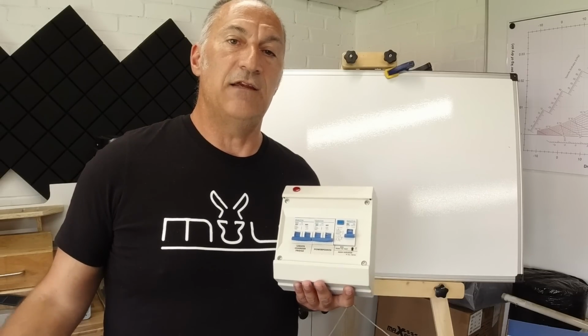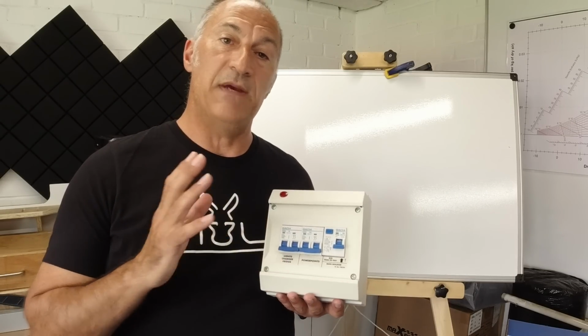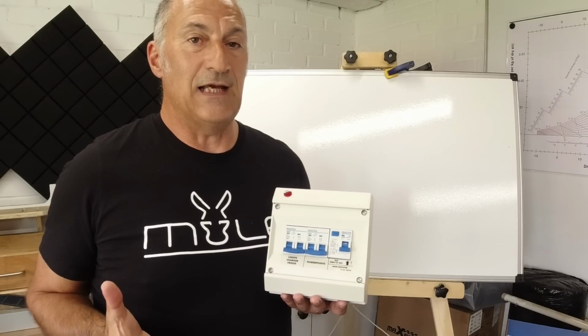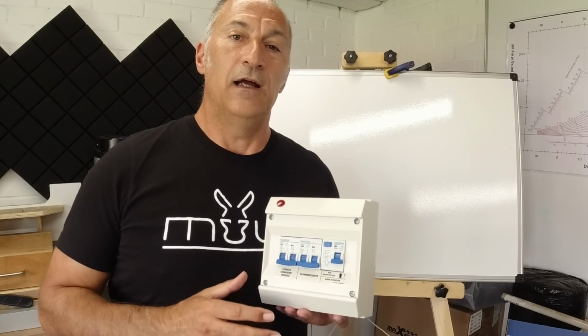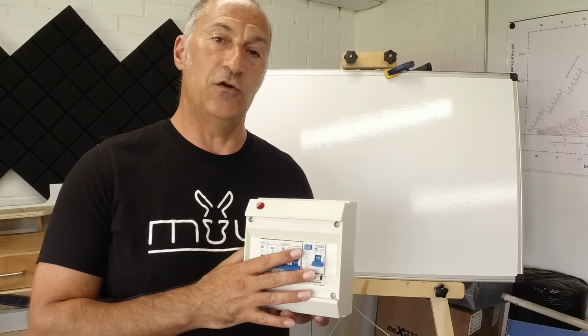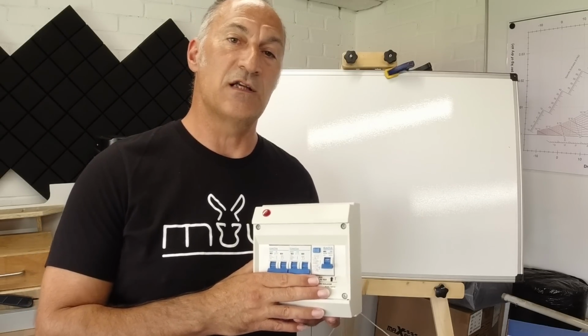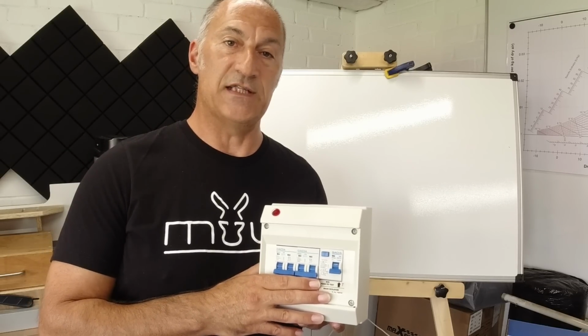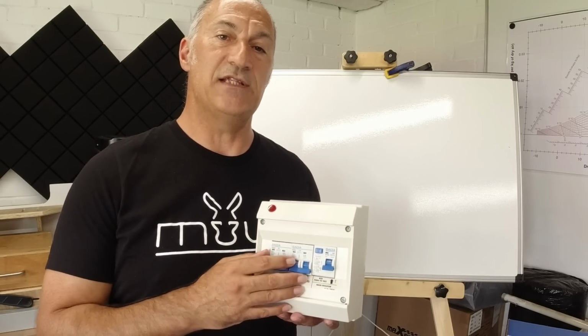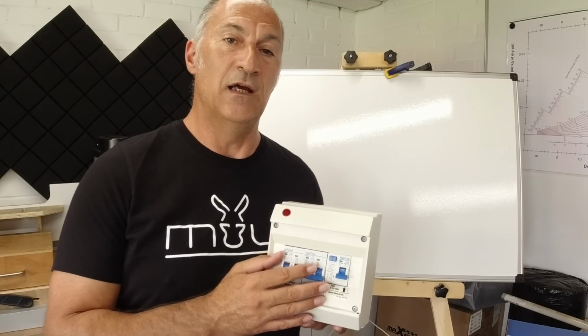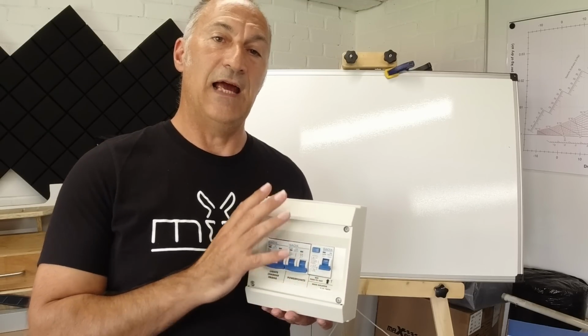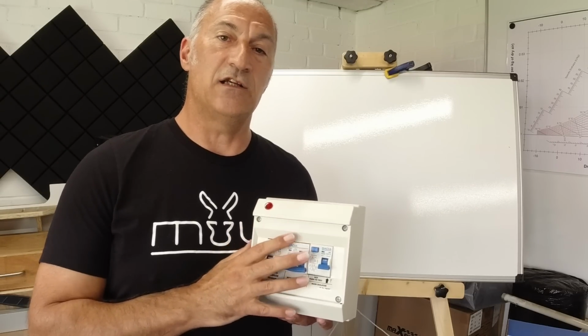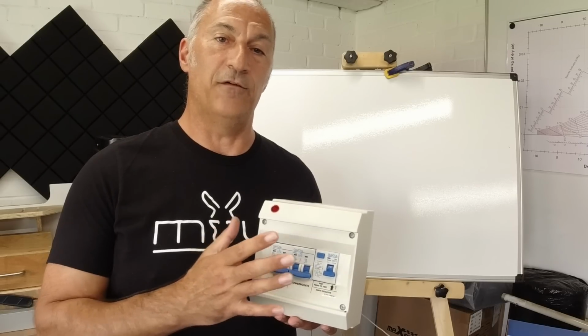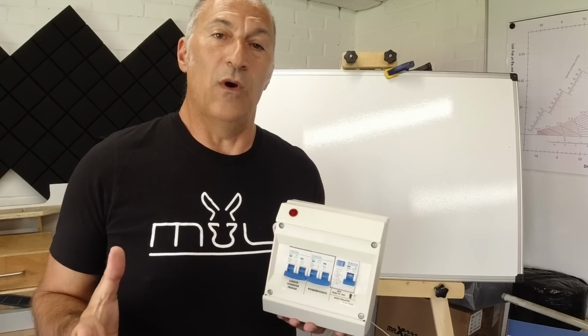Because the current 18th edition wiring regulations for domestic dwellings, so I guess they're referring to houses, now has the requirement for the consumer unit to be a metal clad box. And this is for the reasons of fire protection. If anything happens internally within the consumer unit which causes a fire, then having this in a metal box is going to restrict the outbreak of the fire from the consumer unit to wherever it's housed.